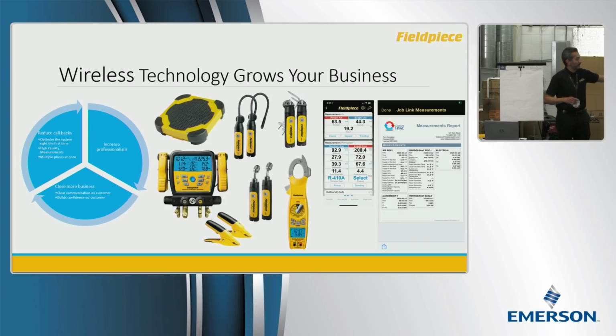What you can do with the application is use the freeze button. Each container, whether for refrigerant charge, airflow, or whatever, has a freeze button. If you're in a location where the run is too long, go to one side of the system first, take those measurements, and press freeze. That locks the readings in so you can go to the other part of the system, do the same thing, lock those in, and generate the report with your measurements. It's as simple as pressing the freeze button to hold them in there.